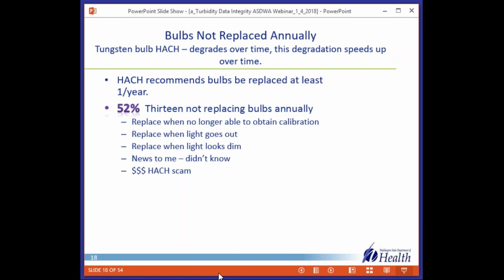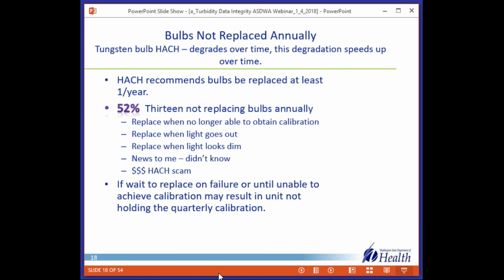Turning to the smoke detector comparison, we think it's probably better to replace your batteries on a routine basis instead of waiting to find out your smoke detector doesn't work. So in the turbidity world, if you wait to replace on failure or until you're unable to achieve calibration, then that can result in the unit not holding the quarterly calibration. So it's something you'll probably hear from us a lot. I think you have to follow the equipment manufacturer's recommended maintenance schedule in most cases.